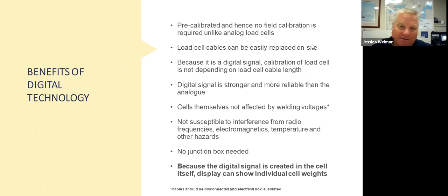In addition, the cells themselves, because we talked about the sensing element is not in contact with the metallic case of the unit, you can weld on a frame that has our cells mounted and not worry about damaging the cell. You have to disconnect the electronics around it because you can fry the boards inside the controller if they're not electrically isolated, but the cell itself can stay on the skid. That's a big deal because if you have a heavy vessel sitting on top of a strain gauge cell, you have to remove the strain gauge before you weld on the frame. Ours are less susceptible to radio interference, any kind of electrical interference.